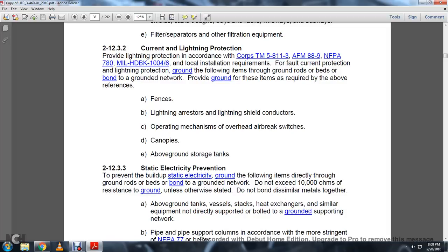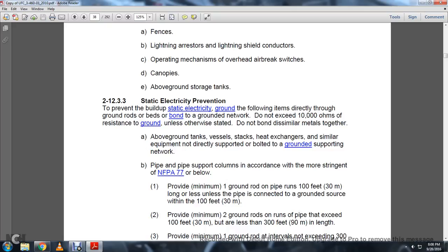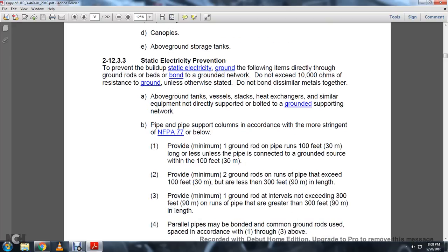Alright, 212.3.3 Static electricity prevention. To prevent buildup of static electricity, ground the following items directly through ground rods or beds to the ground network. Do not exceed 10,000 ohms of resistance to ground unless otherwise stated. Do not bond dissimilar metals together. Aboveground tanks, vessels, stacks, heat exchangers, and similar equipment that are not directly supported should be bolted to the ground supporting network. Pipe and pipe support columns: in accordance with the more stringent of NFPA 77 or the following. Provide a minimum of one ground rod on pipe runs of 100 feet or less, unless the pipe is connected to a ground source within 100 feet.